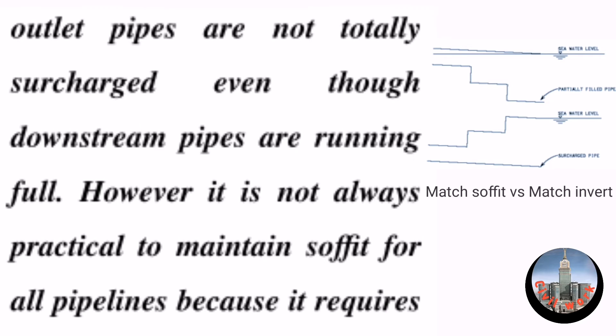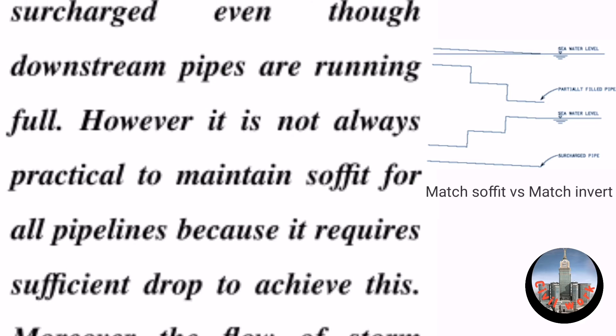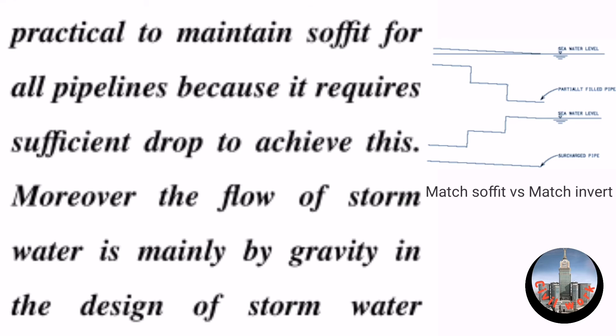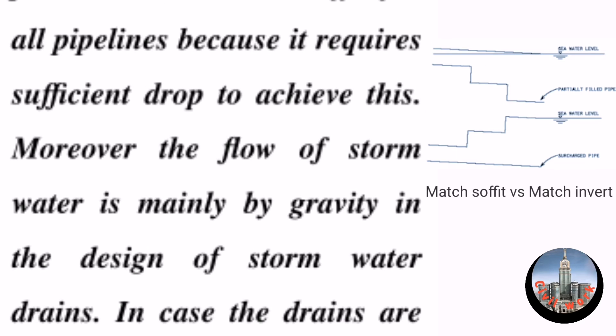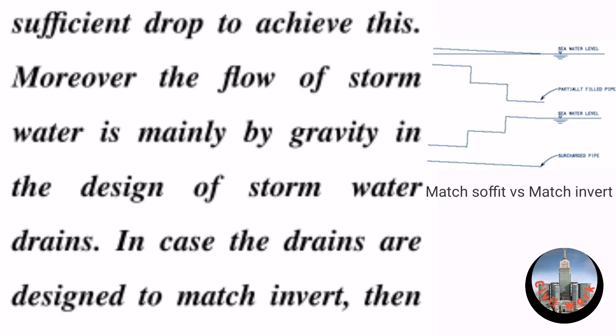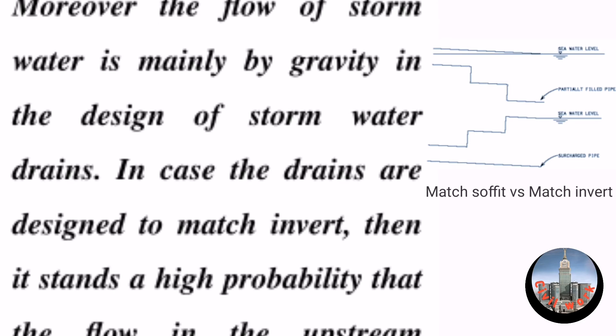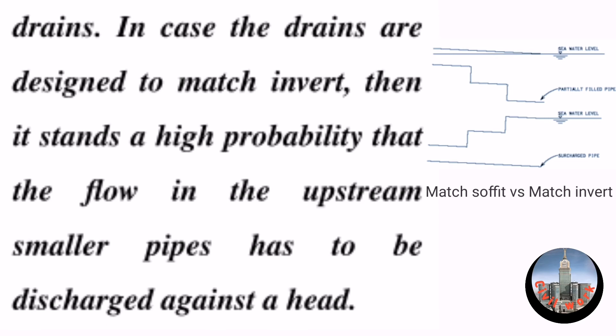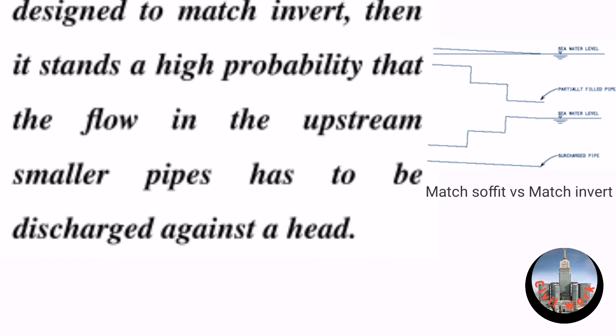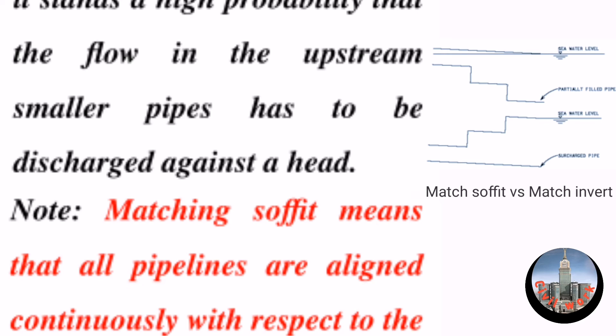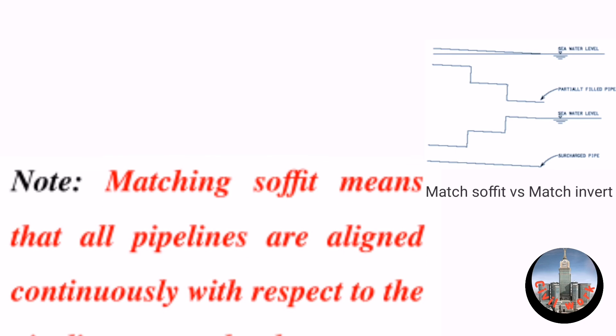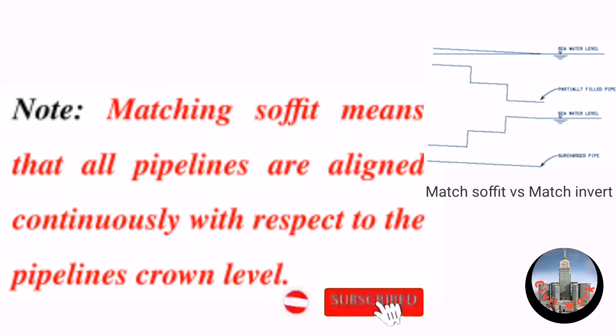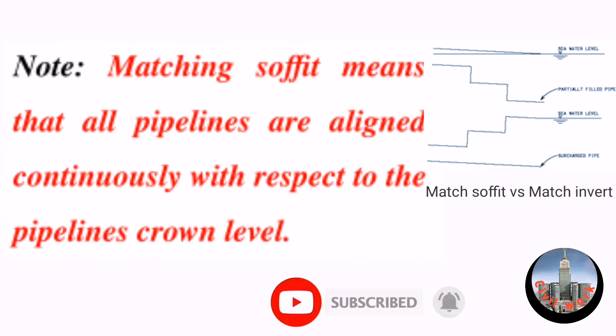However, it is not always practical to maintain soffit for all pipelines because it requires sufficient drop to achieve this. Moreover, the flow of stormwater is mainly by gravity. In the design of stormwater drains, if the drains are designed to match invert, then there is a high probability that the flow in the upstream smaller pipes has to be discharged against a head. Matching soffit means that all pipelines are aligned continuously with respect to the pipelines' crown level.